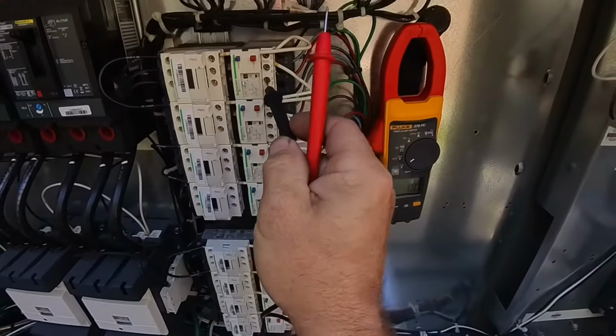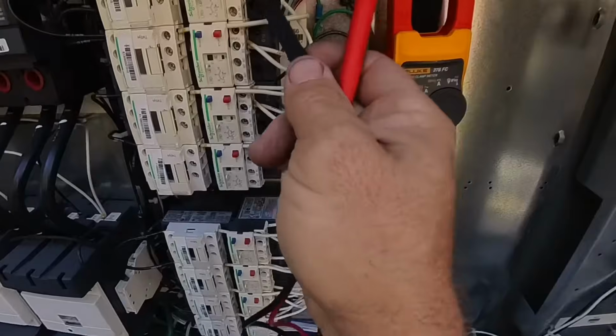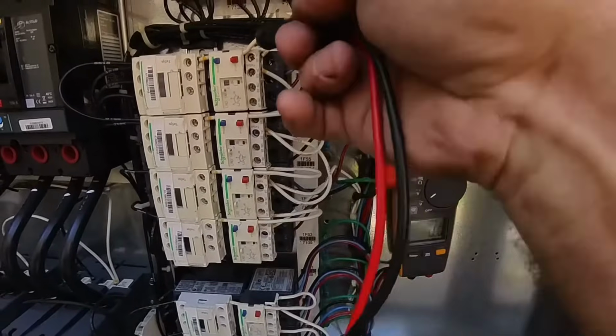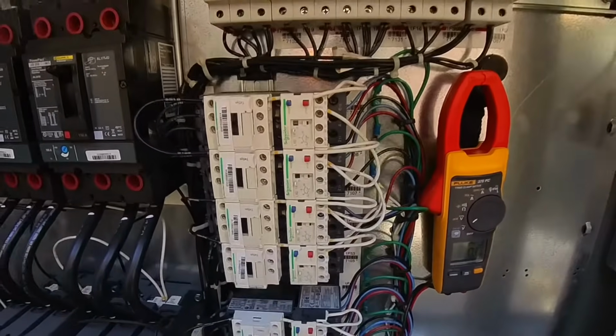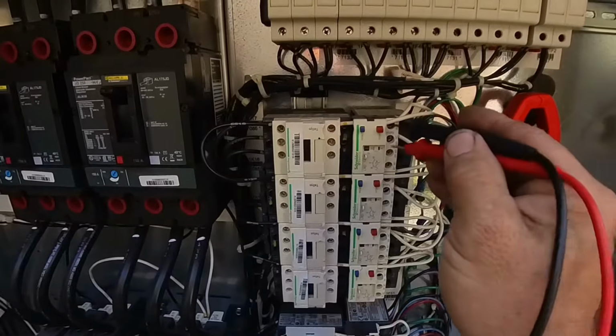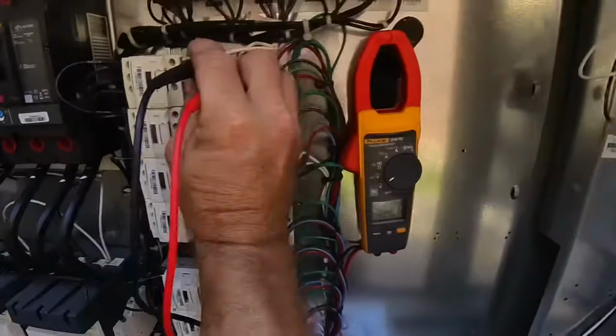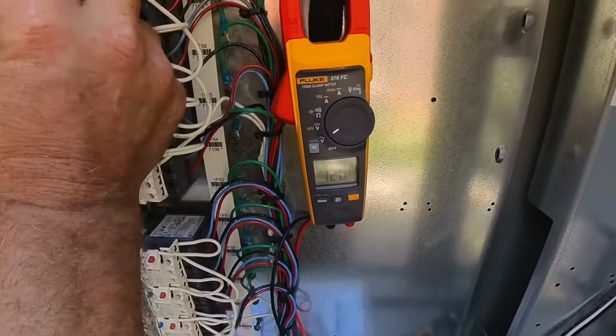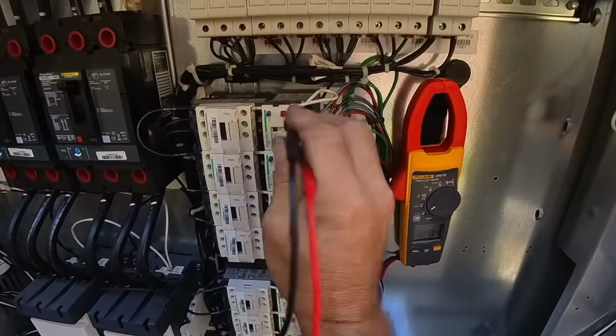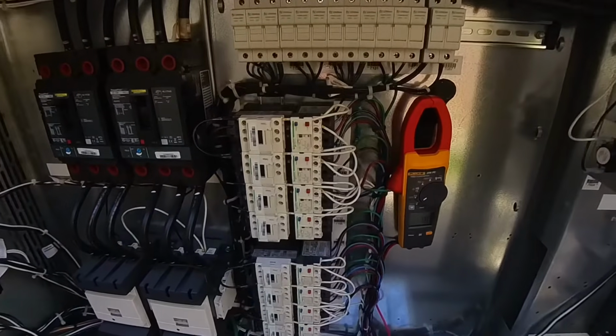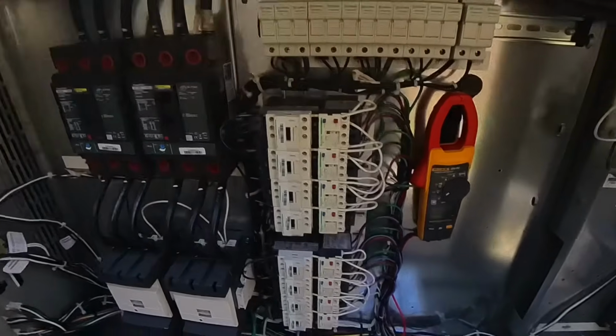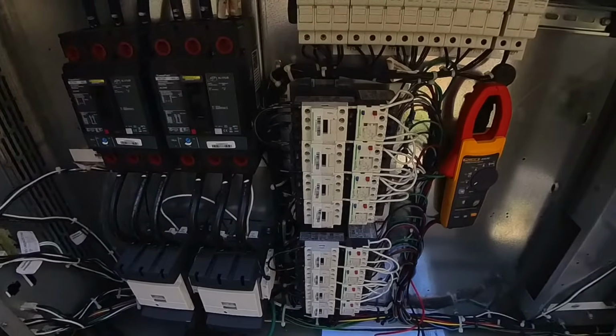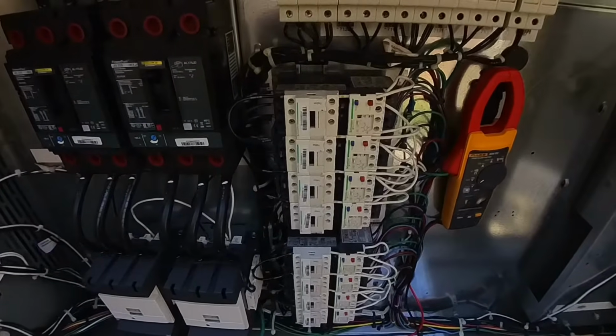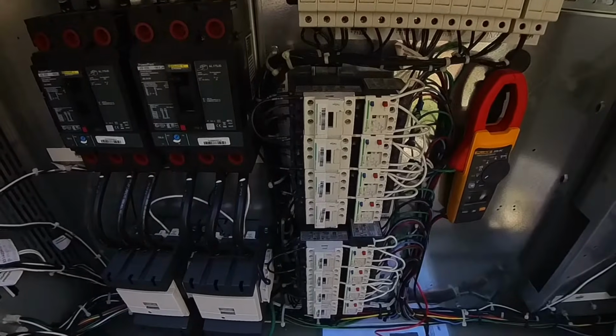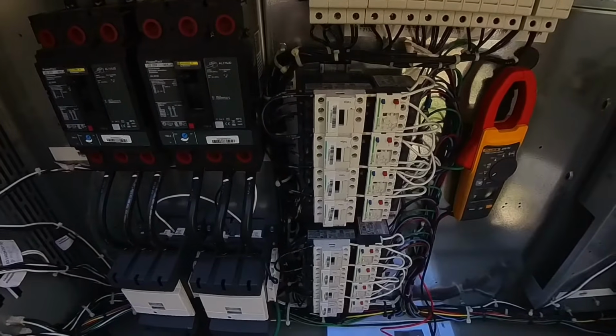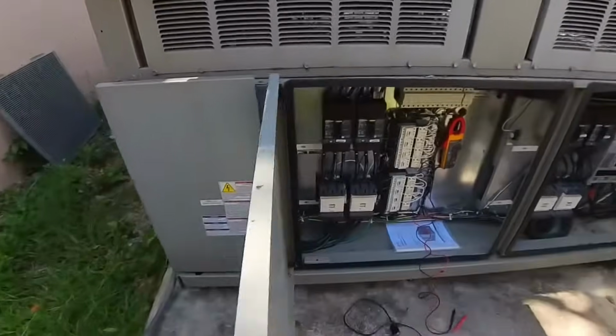Alright, so the overload is here, and we have normally closed between 95 and 96. So I shouldn't get a reading there. I am getting 120 volts. So this overload is tripped. Reset that. We have the plug is obviously disconnected up there, and just verify it's not moved.